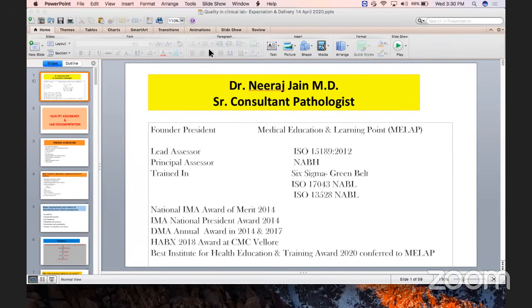You can use retained sample as IQC for the time being, and you get one letter from the company people saying that in this time controls are not available, so that your intention is clear, you want to buy, but those controls are not available. But for retained sample, you shall have some acceptability criteria. Understood. So these acceptability criteria you have to develop for your hemoglobin, for your TLC, for your platelet, for your RBC. I'm talking in relation to hematology. For your biochemistry, you have to develop acceptability criteria for different parameters.